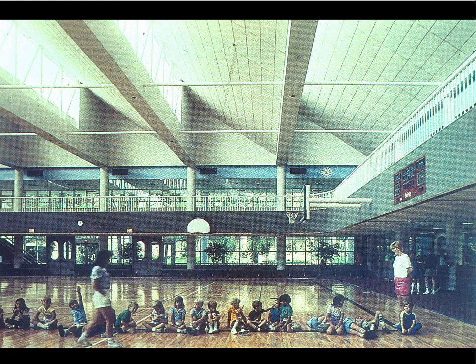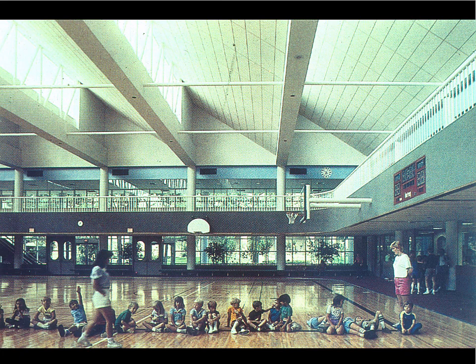There are examples where the task differs significantly from a library or office. In a library or office there's a hypothetical surface representing the tabletop or desktop. But in a gymnasium the task is not a paper task — it's following the flight of a basketball, so the space must be bright throughout its entire volume. You'll notice the height to the top of the glazing is much greater than the spacing between glazing elements, because we want to keep the entire volume of the space beautifully illuminated.